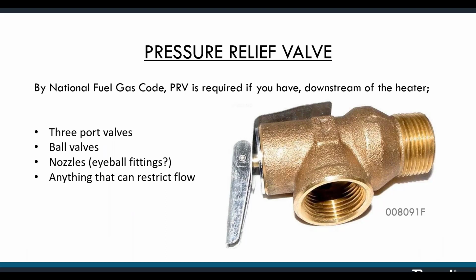This is our pressure relief valve. The National Fuel Gas Code requires a pressure relief valve if you have anything downstream of the heater that might restrict flow. The code specifically uses the word nozzles at one point. I would think that eyeball fittings in the plaster could be considered nozzles.